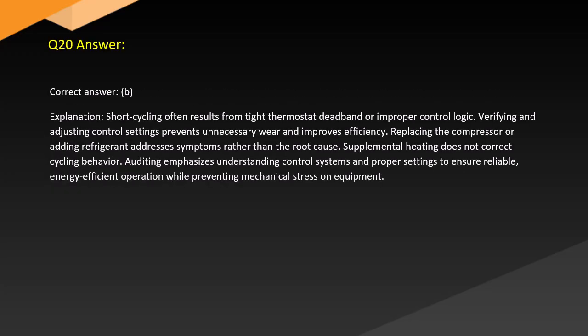Answer. Correct answer. B. Explanation. Short cycling often results from tight thermostat deadband or improper control logic. Verifying and adjusting control settings prevents unnecessary wear and improves efficiency. Replacing the compressor or adding refrigerant addresses symptoms rather than the root cause. Supplemental heating does not correct cycling behavior. Auditing emphasizes understanding control systems and proper settings to ensure reliable, energy-efficient operation while preventing mechanical stress on equipment.